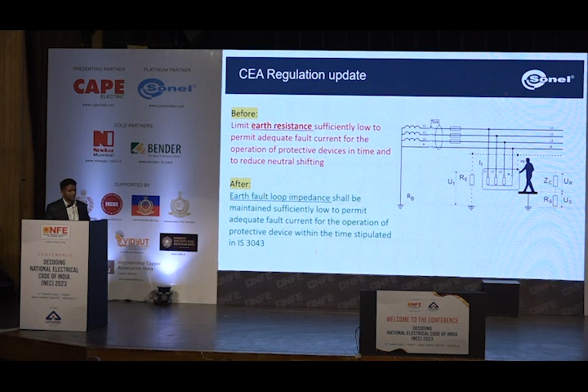This is again an extract copy which is not published yet. You can go to the regulation part of the CEA and you'll be able to see it. Continuously it is mentioned that you have to test your impedance value, and you need to understand what the value of your impedance is - not once, at multiple locations. It's just a screenshot from the CEA guidelines. They've also mandated the use of a loop impedance meter.